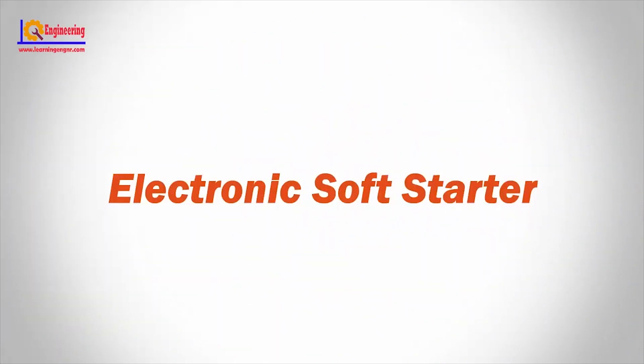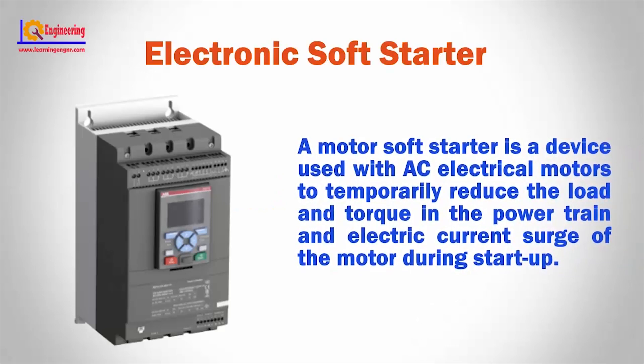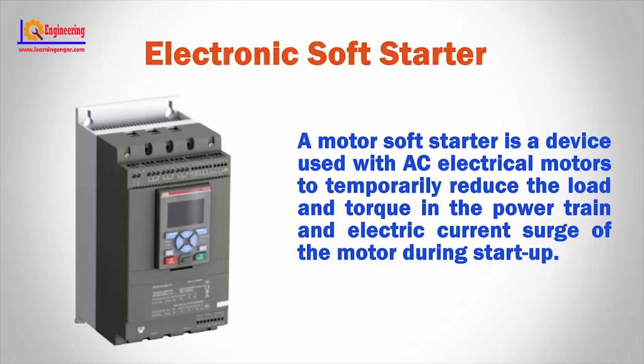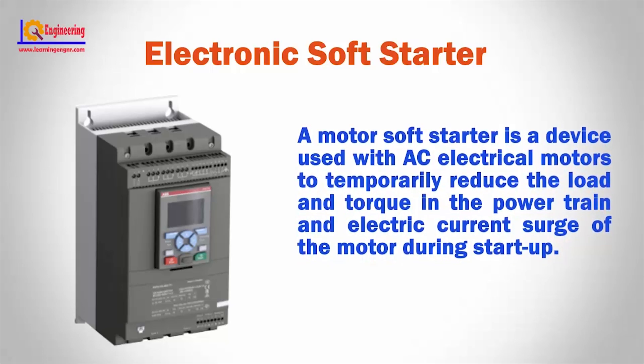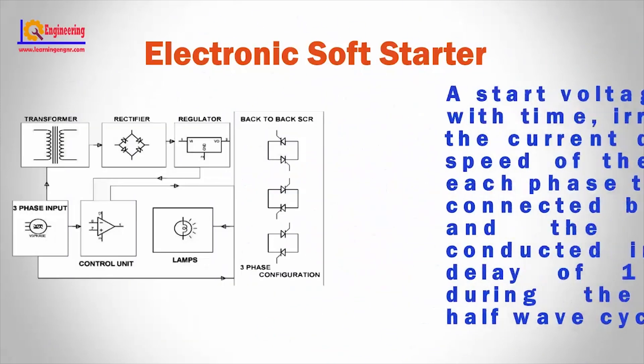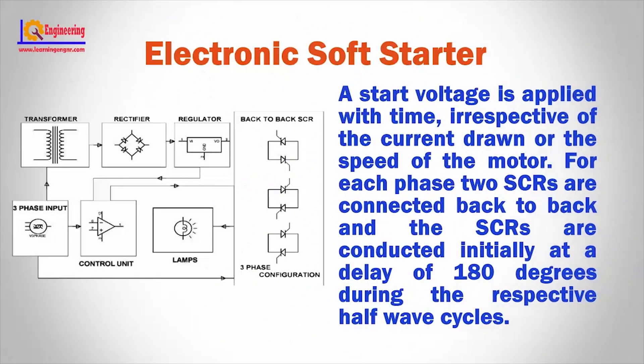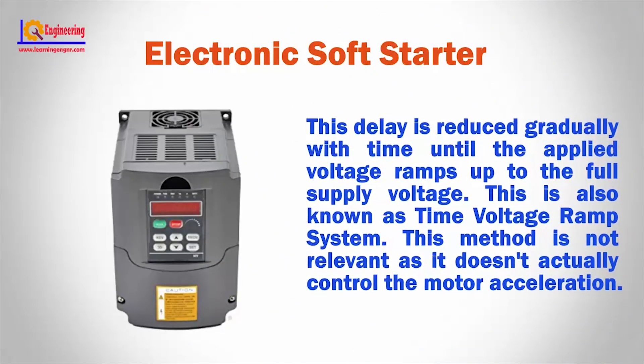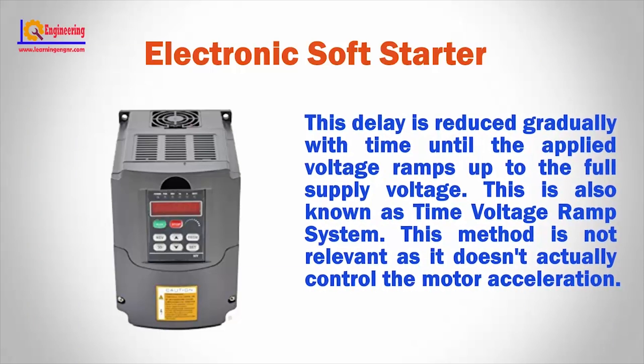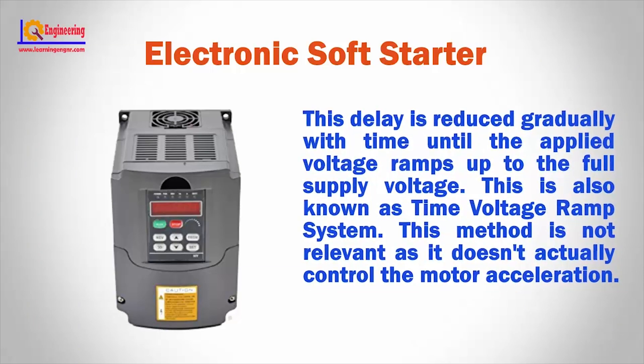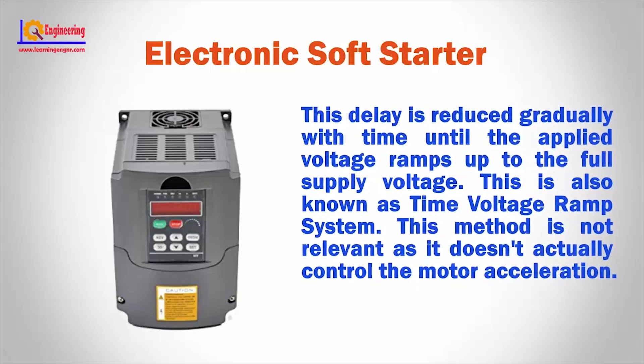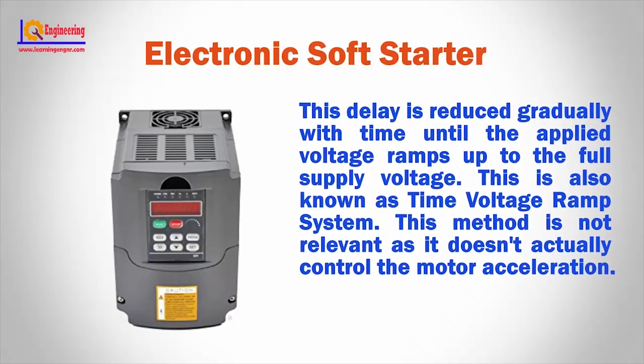Electronic soft starter. A motor soft starter is a device used with AC electrical motors to temporarily reduce the load and torque in the powertrain and electric current surge of the motor during startup. A start voltage is applied with time, irrespective of the current drawn or the speed of the motor. For each phase, two SCRs are connected back to back, and the SCRs are initially conducted at a delay of 180 degrees during the respective half-wave cycles. This delay is reduced gradually with time until the applied voltage ramps up to the full supply voltage. This is also known as the time voltage ramp system. This method is considered limited as it doesn't actually control the motor acceleration.